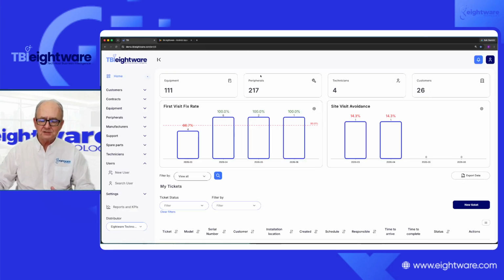What can your customer do with the app? They can create tickets by scanning the QR code, which you have to stick on the instrument. They can also check the status of the tickets, and they will also be able to check the preventive maintenance schedule. Once you program that, they just scan the QR code and will be able to check the PM schedule, not needing to call you or ask for this information.